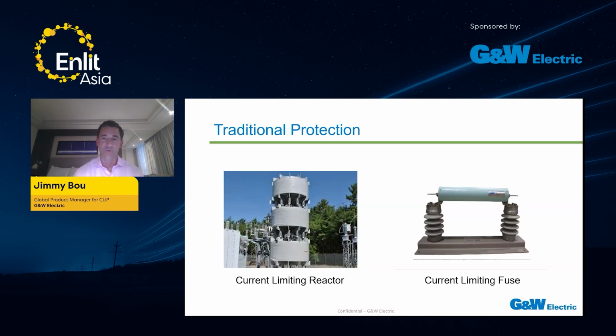And this slide shows you a comparison on size on both solutions, right? Current limiting fuse and your current limiting reactor. You can notice there how a reactor can be up to 3 stories high, while the current limiting fuse is more compact in size, can get up to, that particular one is 1200 millimeters by 600 millimeters, just for reference.